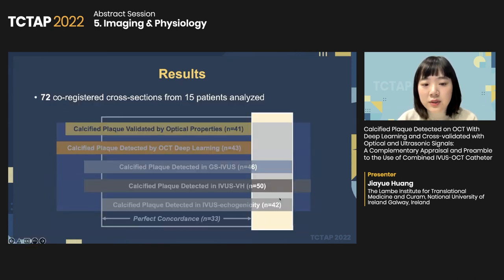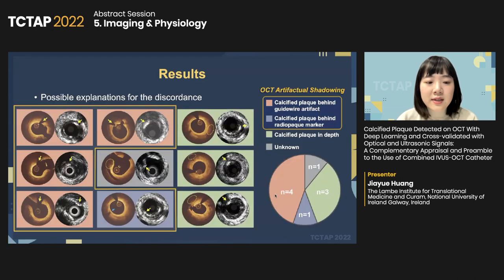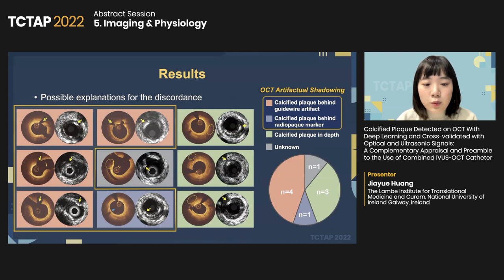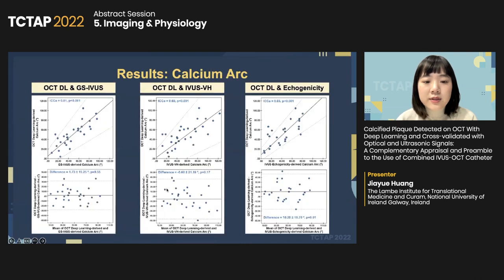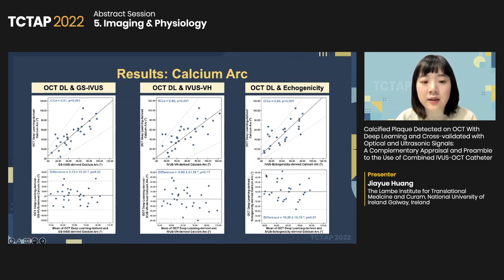We further looked into nine discordant cases where calcified plaque was detected only by ultrasound signals. More than half of the discordant cases occurred when the calcified plaque was hidden behind OCT artifact shadowing, caused either by guidewire artifact or radio-opaque marker. Three others were possibly caused by relatively shallow penetration depth. After excluding five cases with optical confounding factors, there was significant improvement in concordance. OCT deep learning showed substantial agreement with grayscale IVUS, echogenicity, and virtual histology.